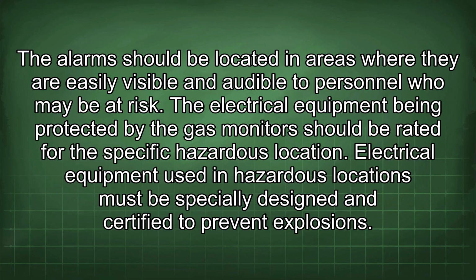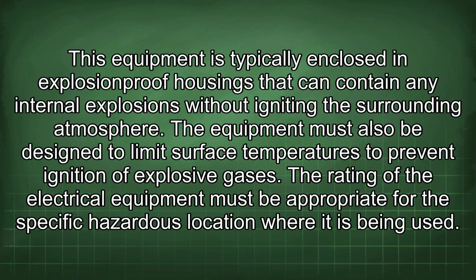The electrical equipment being protected by a gas monitor should be rated for the specific hazardous location. Electrical equipment used in hazardous locations must be specially designed and certified to prevent explosions. This equipment is typically enclosed in explosion-proof housings that can contain any internal explosions without igniting the surrounding atmosphere. The equipment must also be designed to limit surface temperatures to prevent ignition of explosive gases.